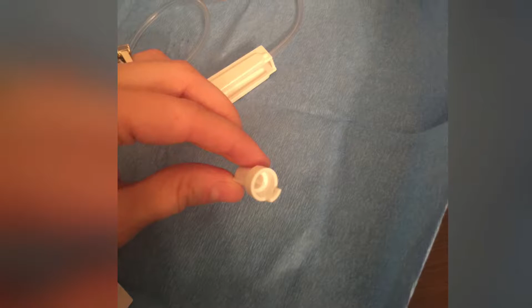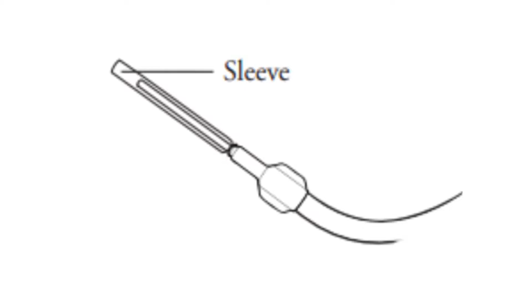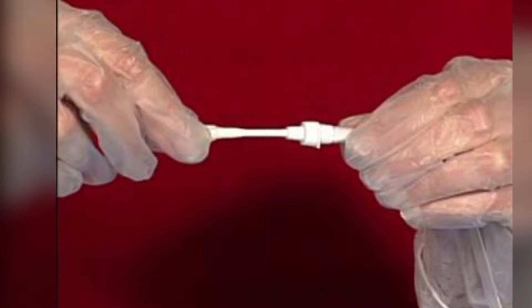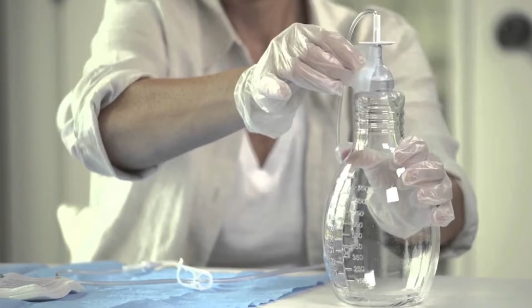Twist off the cap from the valve of the PleurX catheter and discard it. Continue to hold the PleurX catheter. Keep the valve from being contaminated. Take an alcohol wipe and clean the catheter valve thoroughly. Continue to hold the catheter while discarding the alcohol wipe. Pick up the drainage line with your other hand and remove the plastic sleeve. Insert the tip of the drainage line into the clean catheter valve. You will hear and feel a snap when the tip and the valve are locked together.